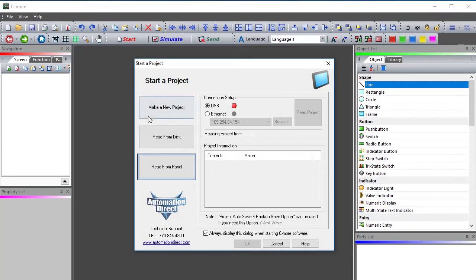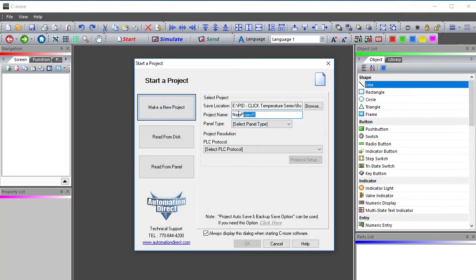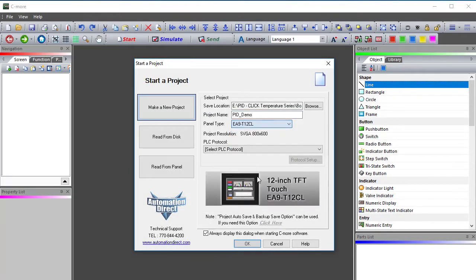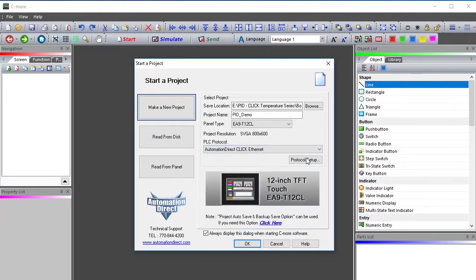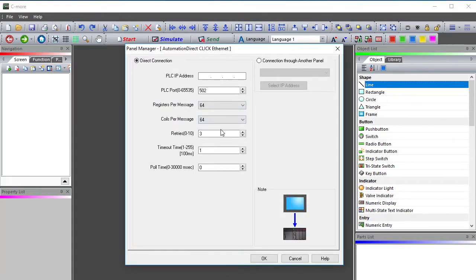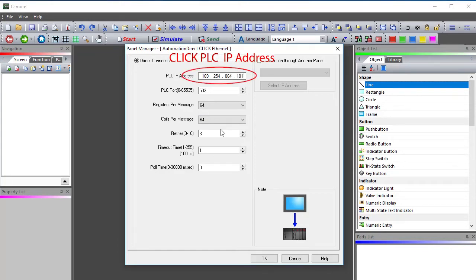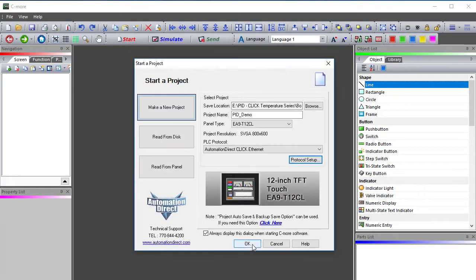I'll bring up the C-more app, make a new project, and give it a name. I'll select the panel that we're using in this demo and select the CLICK PLC Ethernet protocol since that's what we'll be using. Click on Protocol Setup and enter the IP address of the CLICK PLC from the network block diagram — that's not the C-more HMI's IP address, it's the CLICK PLC's address. Then hit OK a couple times to exit.